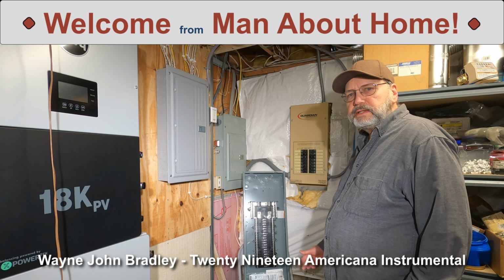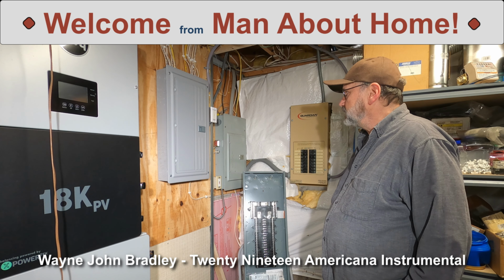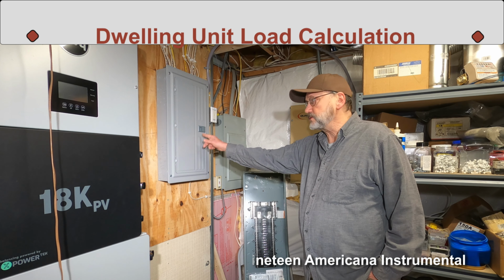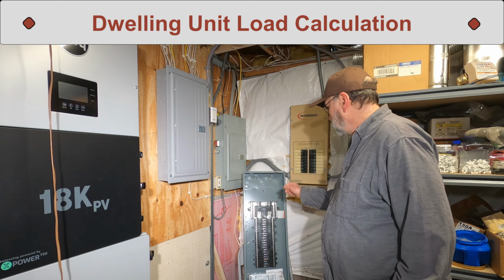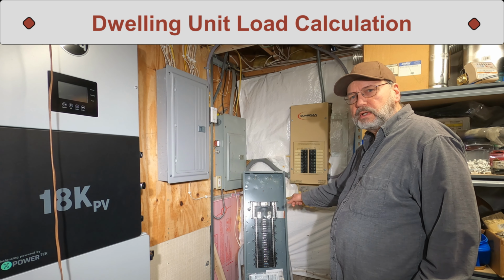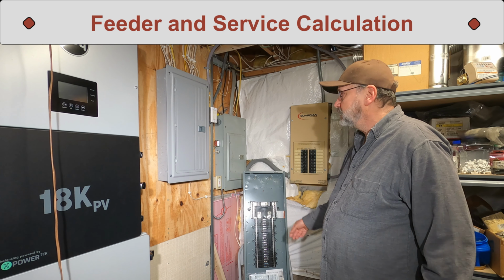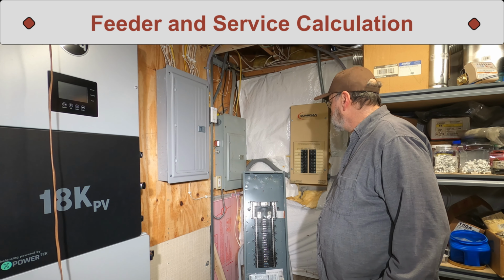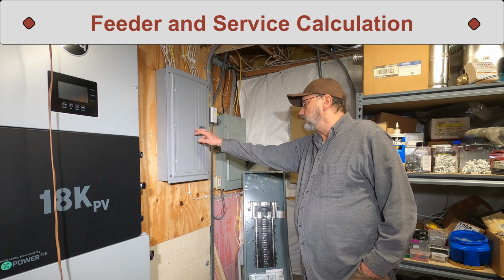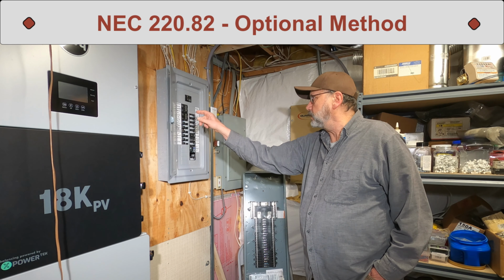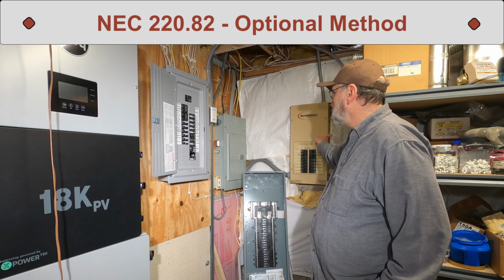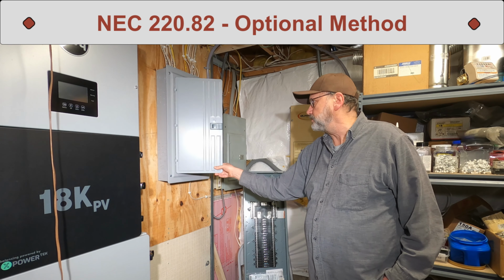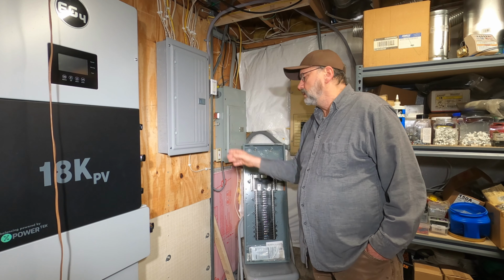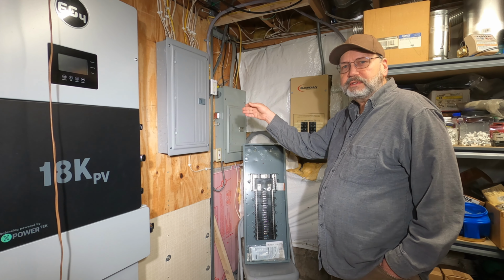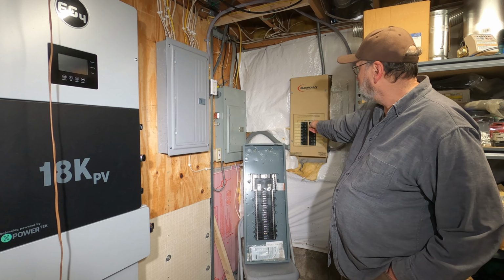So what I've got going on here today is I need to do the load calculations for the new sub panel that's already in service and the new main panel that I'm planning to install anyway. And I already know that this 100 amp main breaker and this panel and the cable I installed are adequate to serve this panel, because we're running the house off it, being fed from over here.